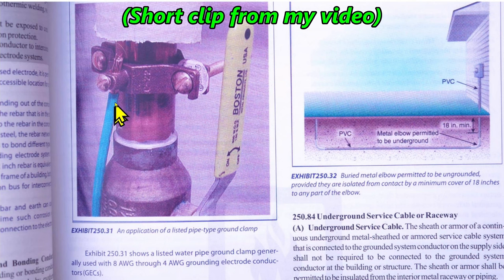See this green wire right here? That is a grounding electrode conductor, or GEC. And this is exhibit 250.31 from the 2020 NEC handbook. And it says exhibit 250.31 shows a listed water pipe ground clamp. That's right here, the ground clamp, generally used with 8 AWG through 4 AWG grounding electrode conductors, GECs. So there you go. That's a simple example of a GEC.